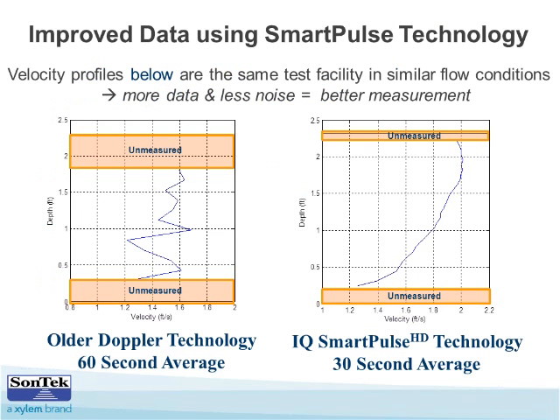That's basically how it works. So what is different now? What does SonTek do that it didn't do before, and what does it do that nobody else does? Well, I like this graphic. What you see on the left there is a pretty standard looking velocity profile. We're looking at a velocity profile from the side there. This would be our water surface. This would be the bottom. The instrument would be right here, sending an acoustic signal back, and this is what the data would look like.